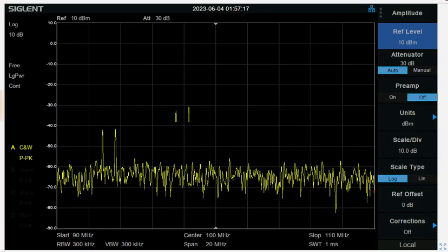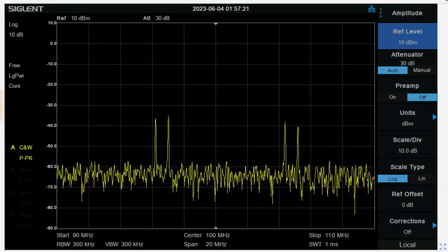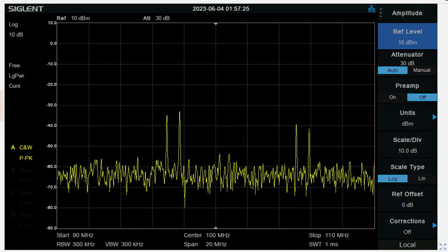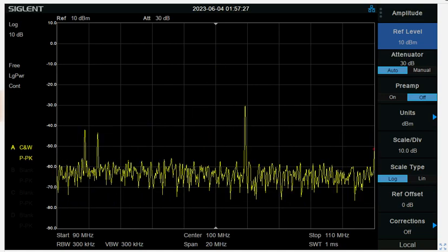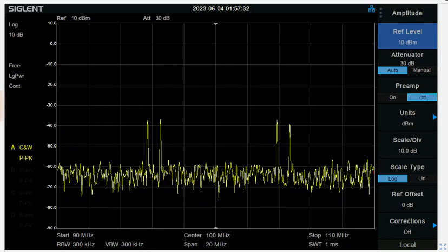And you know, it'd be really nice if we could look at this thing with amplitude versus time. Yeah, we could go get a crystal detector and put it to a scope and yada yada yada, but isn't there a way that the SpecAn can do that for us? And the answer, of course, is yes. It's something called zero span.